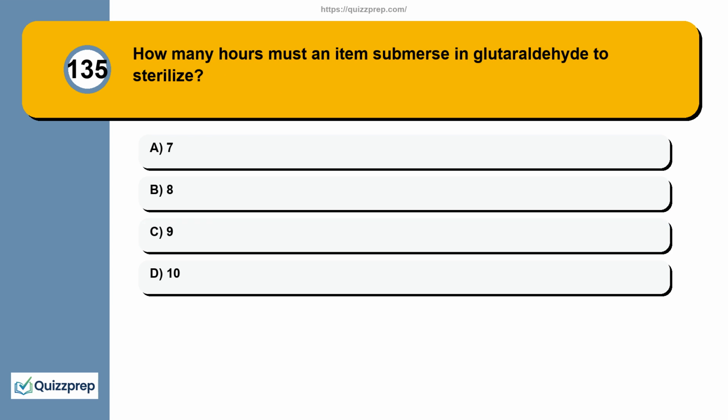Question 135. How many hours must an item submerge in glutaraldehyde to sterilize? Option A, 7. Option B, 8. Option C, 9. Option D, 10. The correct answer is option D, 10.